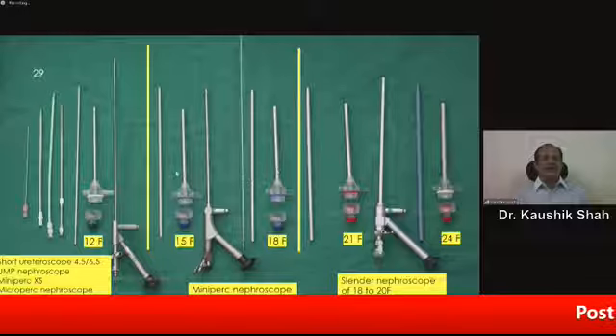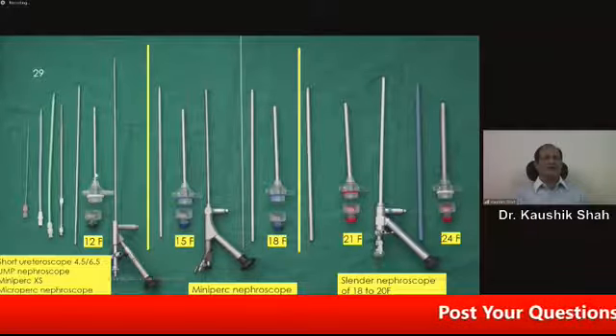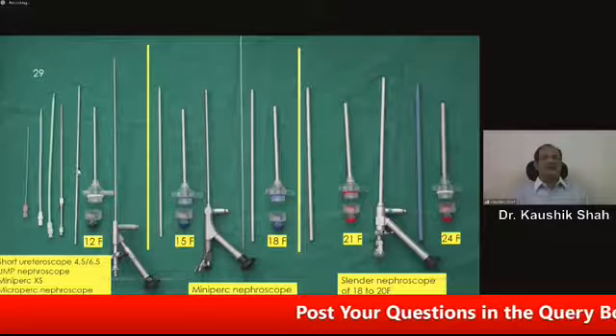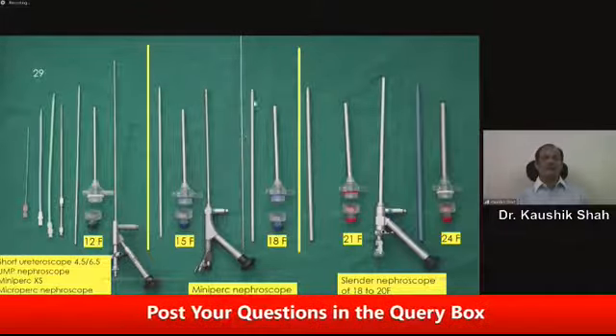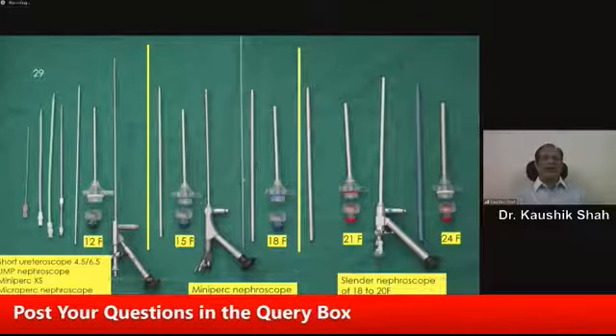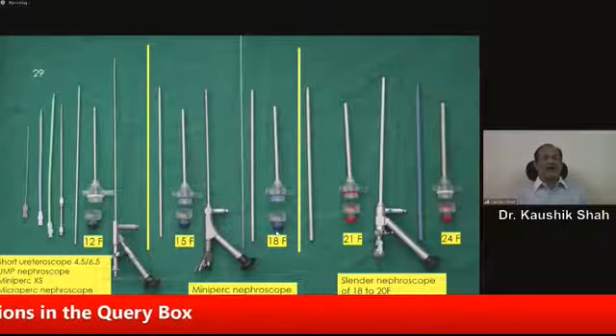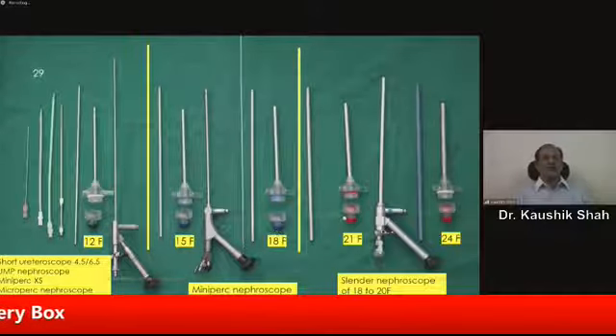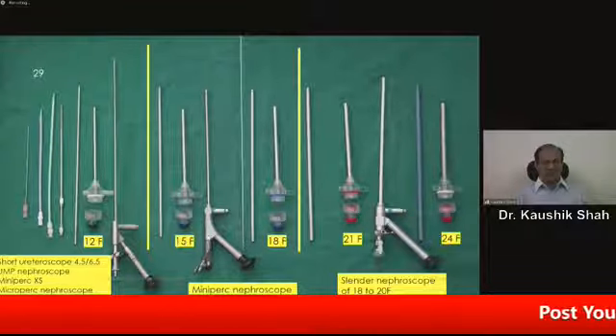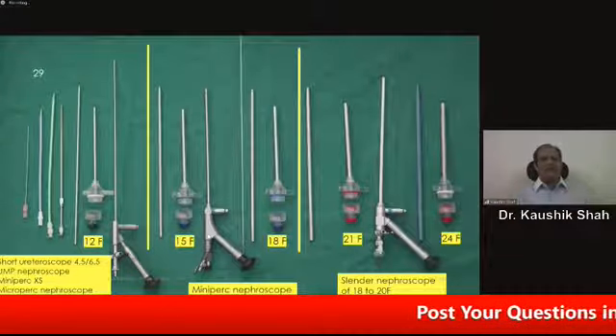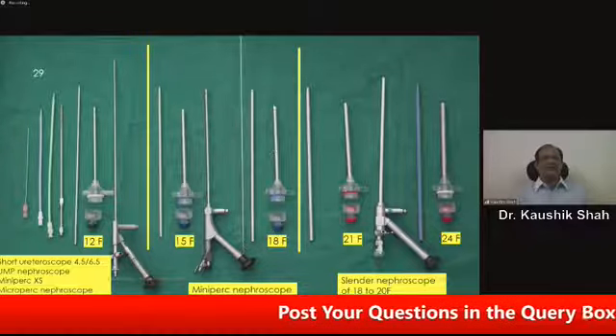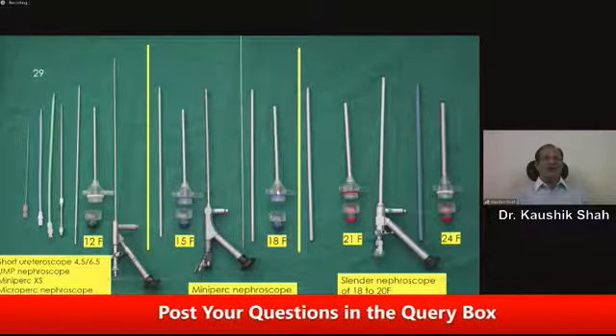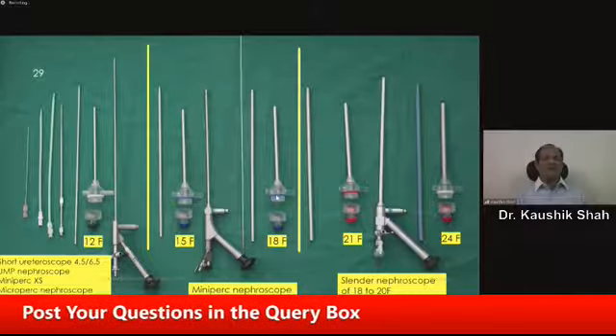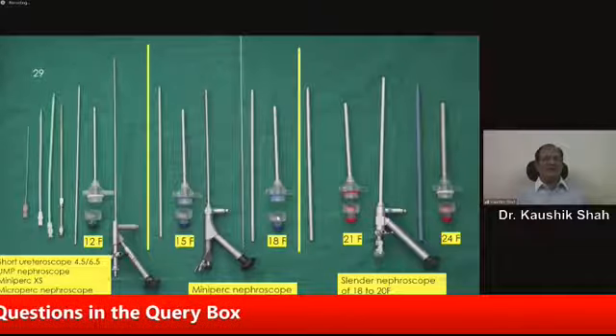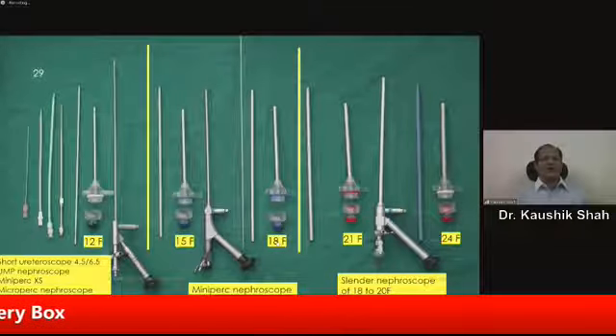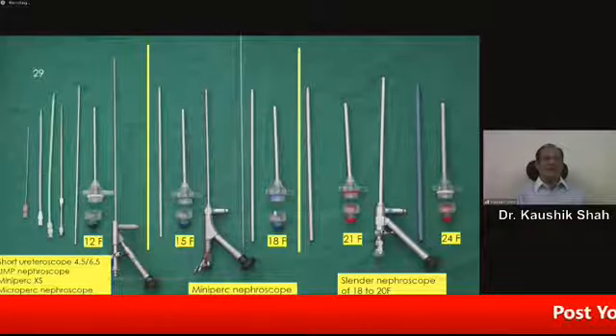This is a part of the system. When you buy a sheath, this is also available, so you don't need to buy it separately. So this dilator you put, an 18 French. The advantage of an 18 French sheath, or even 21 French, is that the miniperc nephroscope occupies very small space. So there is a very large space by the side of the nephroscope which can work as a suction channel, and very large fragments and the dust and everything can be sucked out. Even bigger fragments as big as 5.5 millimeter or 15 French fragments can also be sucked out.